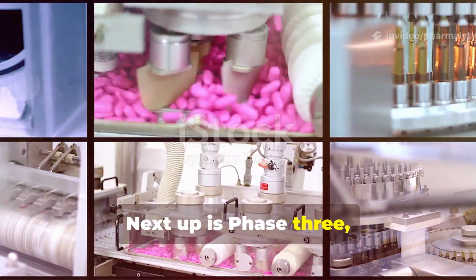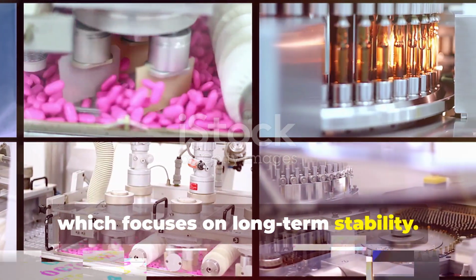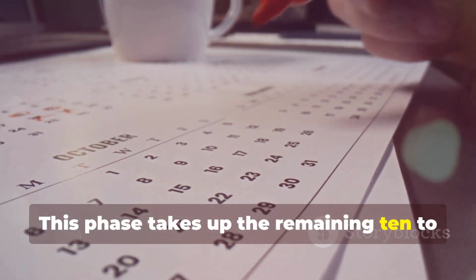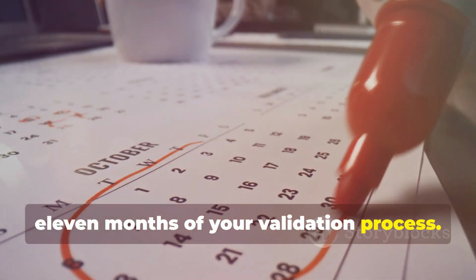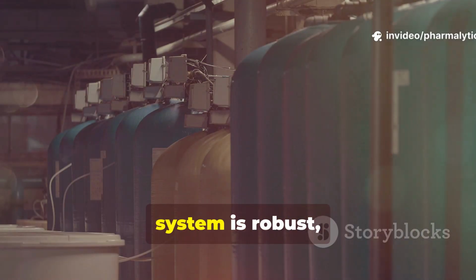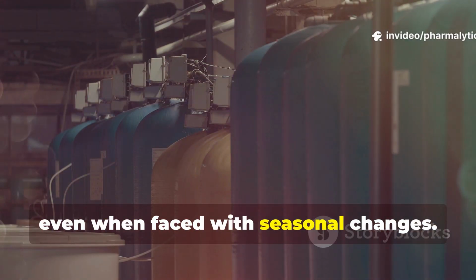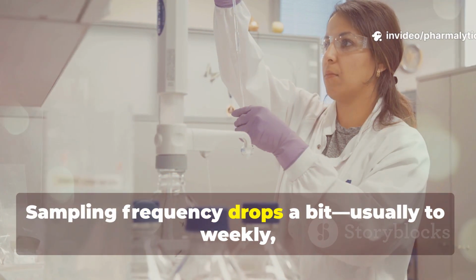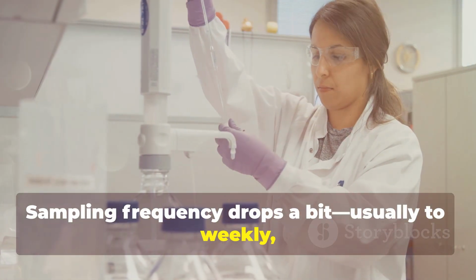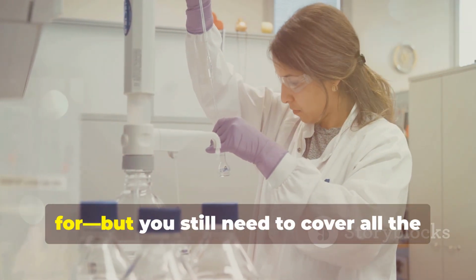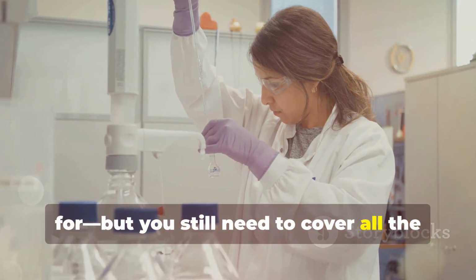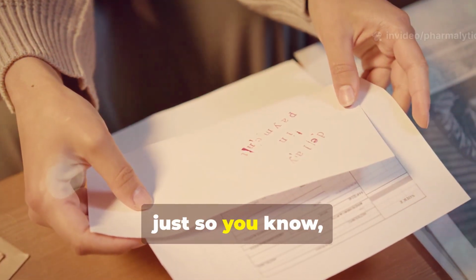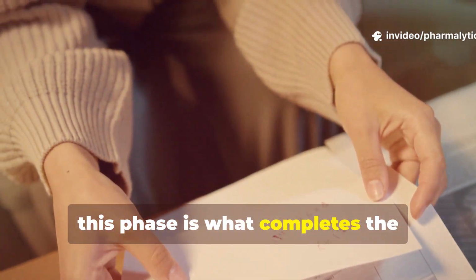Next up is phase 3, which focuses on long-term stability. This phase takes up the remaining 10 to 11 months of your validation process. The goal here is to prove that your system is robust, even when faced with seasonal changes. Sampling frequency drops a bit, usually to weekly, or whatever your routine plan calls for, but you still need to cover all the critical points. And just so you know, this phase is what completes the validation lifecycle.